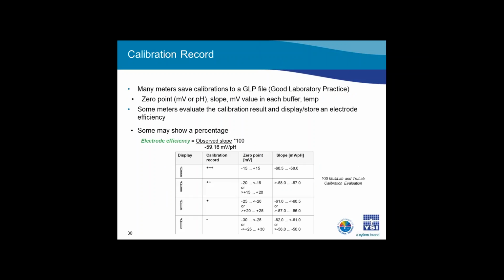As mentioned before, many meters save calibrations in a GLP file, or good laboratory practice file. The number of calibrations stored by a meter is instrument dependent, so check with the operations manual if you're unsure how many records your instrument is saving. Many instruments will allow you to back up the GLP data to a PC, to a computer, or may provide you the ability to print it out.